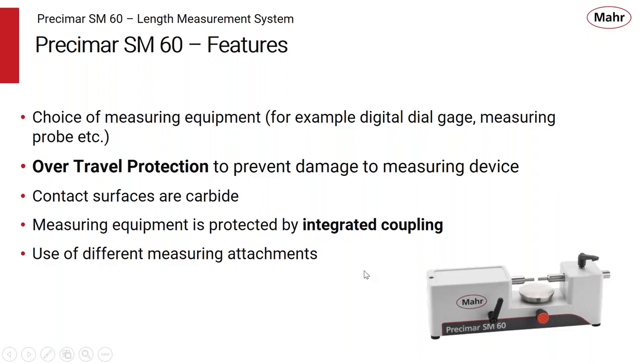We've designed the SM60 to be virtually universal for the type of measuring device readout that you want to have. So for example, you can use dial indicators or digital dial indicators, measuring probes, etc. All depends on the system performance that you may require. One of the nice things about the product is that it has over travel protection, which helps prevent damage to the measuring device. And that's incorporated into the retraction of the anvil. So if you're using a short range probe, for example, with limited range, as you pull the sensitive contact back, you'll feel that it hits the end of travel of the probe, but the handle can keep on going, so you can't force or put too much pressure on the sensitive contact.